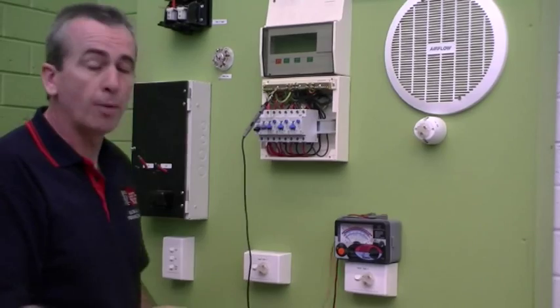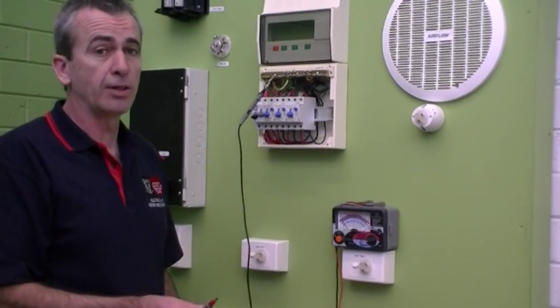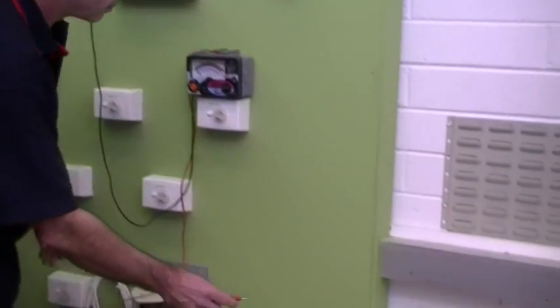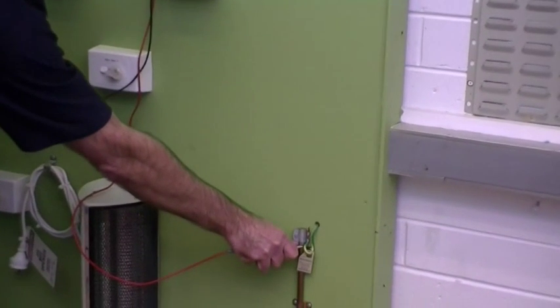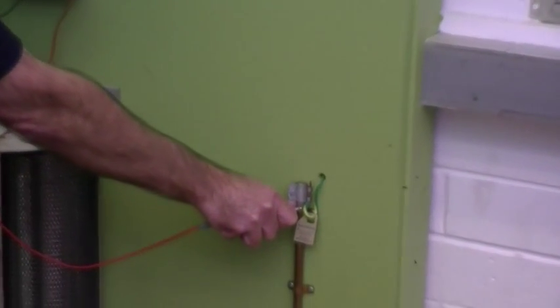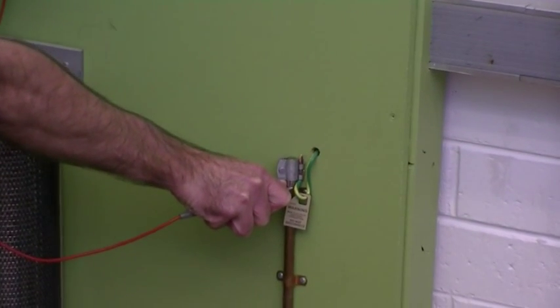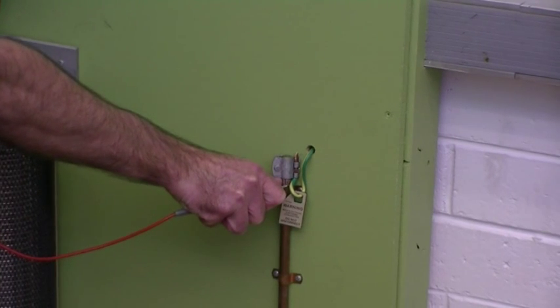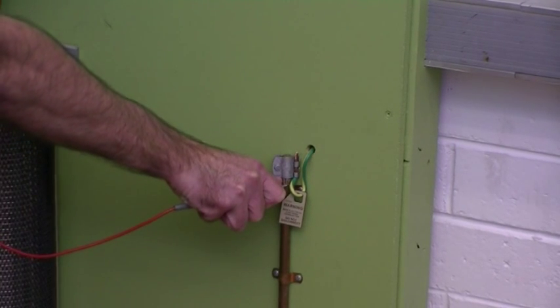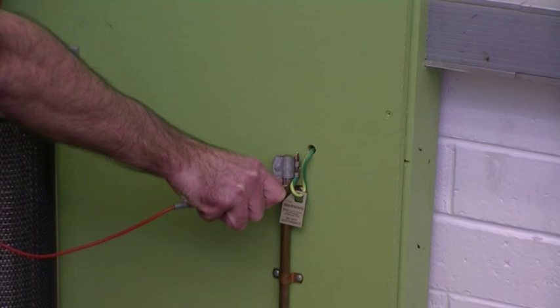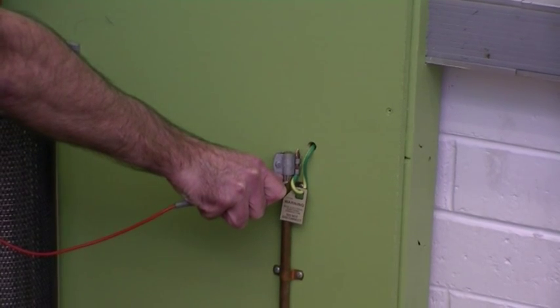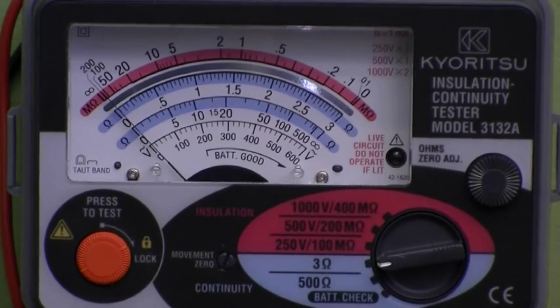With the other probe, I'm now going to go down to the earth electrode. And there's my reading, which is about 0.04 of an ohm, which is a pass because it is well under the maximum allowable 0.5 of an ohm.